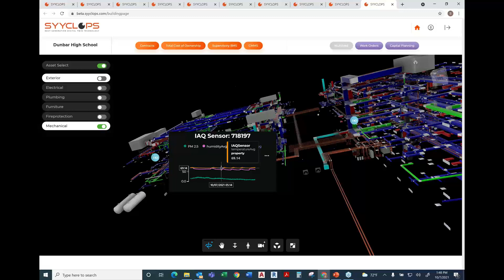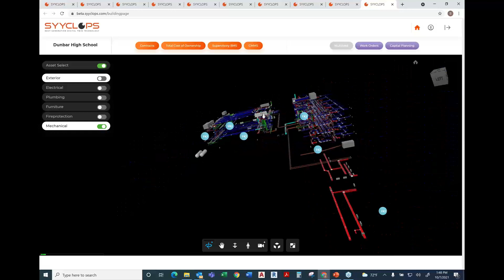As long as we can ingest the sensor data that tells us our current consumption for the last 10 years, if I have sub-metering data on that chiller—let's pretend this is a chiller right here—then I know what I'm going to use. Then I overlay that with the new chiller, which uses kWs per ton. So if my chiller is 500 tons, I know how much kW I use. I can put in those same usage profiles, and then start to run those scenarios.